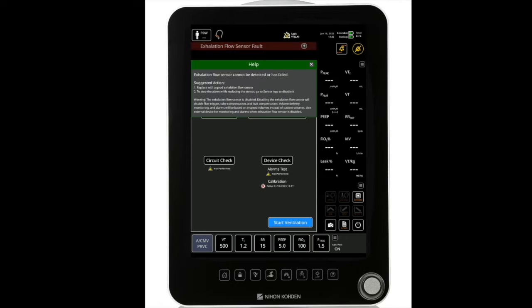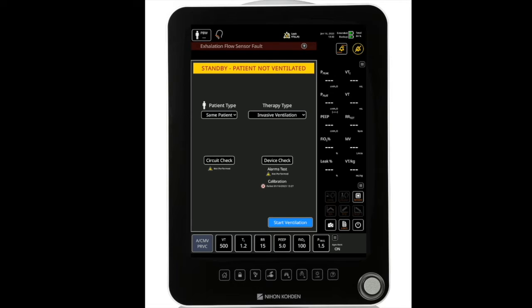If I press the question icon in the alarm message, it's going to give suggestions to correct this alarm. It's going to list replace it with a good exhalation flow sensor, and also to stop the alarm while replacing the sensor, go to the sensor app to disable it.